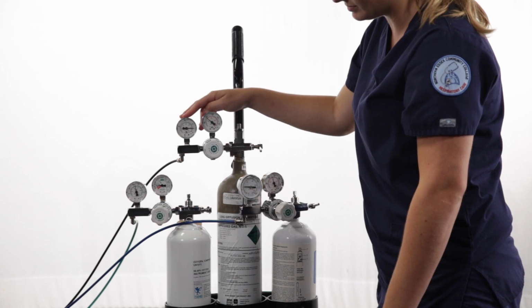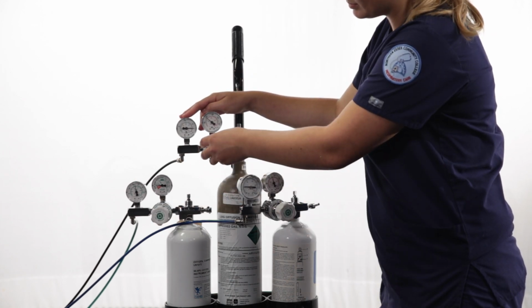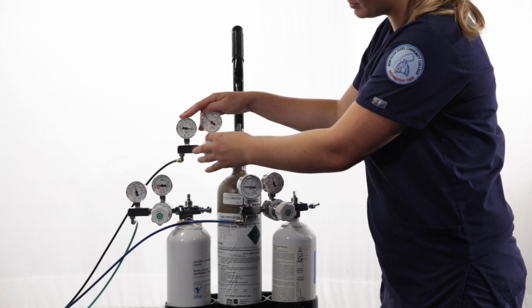We recommend that at the end of the day, the master valve only should be closed, leaving the output pressure valve in its current position.